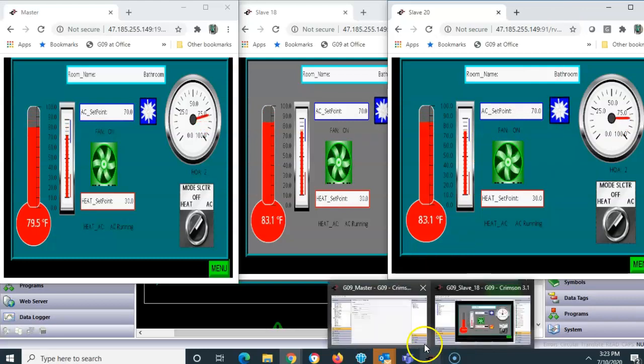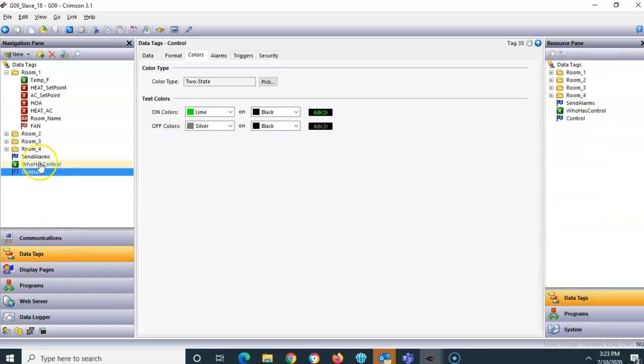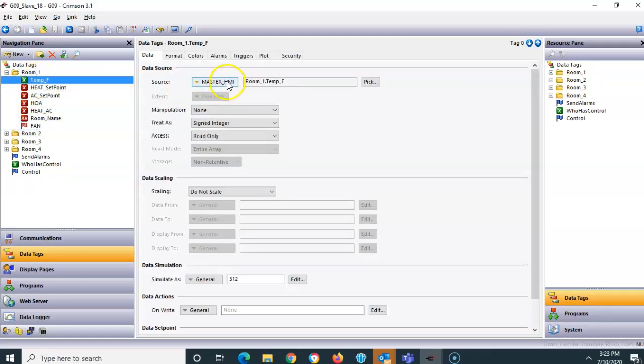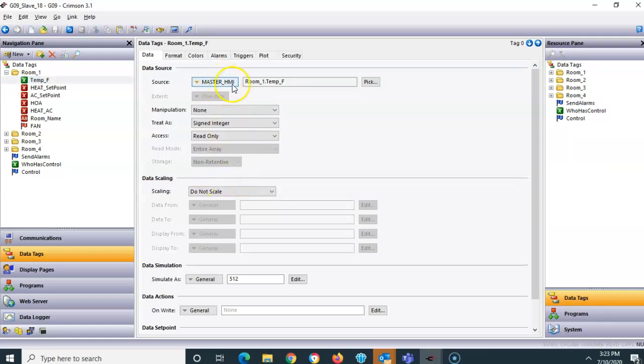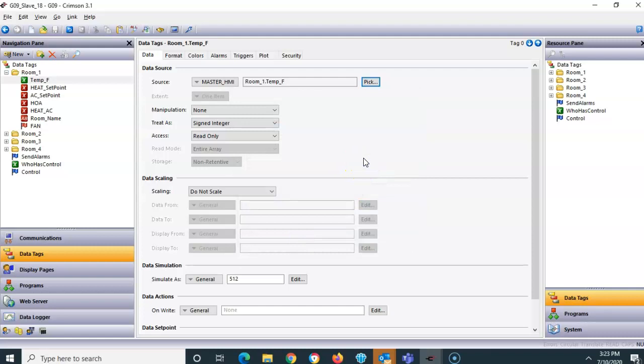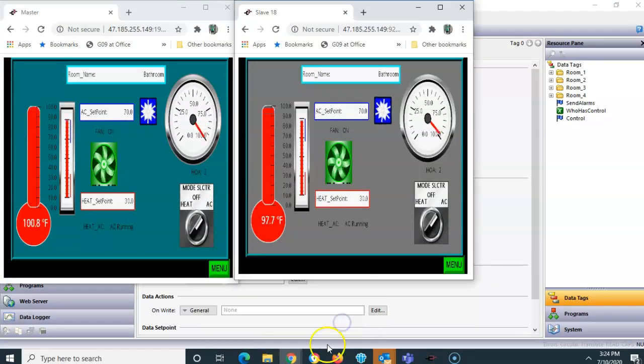One more thing: in the slave's data tags, normally all tags are linked locally, but because I'm using the OPC driver I hit the pull-down and linked them to the master HMI — then hit the pick button to see all the tags. If you're interested in examining these databases, send me an email and I'll be glad to share all three Crimson databases with you.